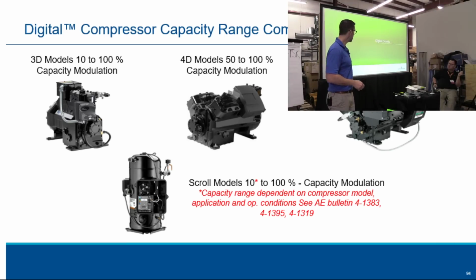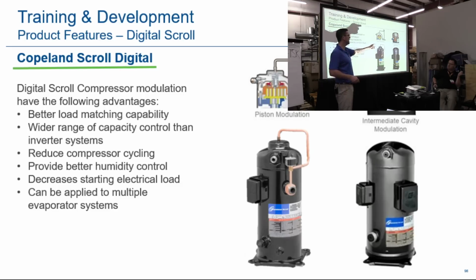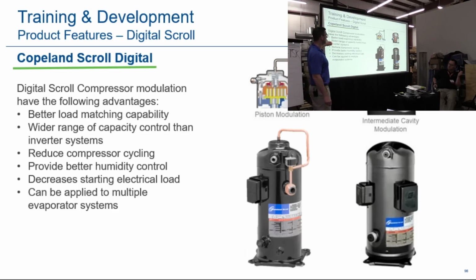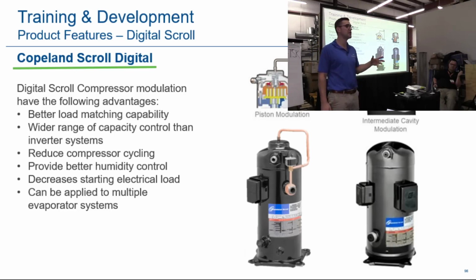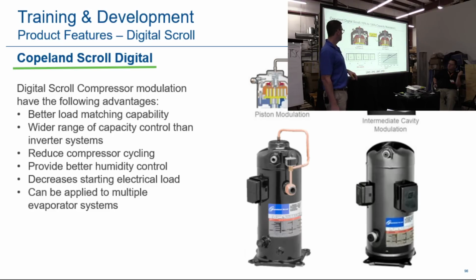Okay, digital scrolls. We have two different designs, a piston type and our larger one, an intermediate type. So you'll have a pipe outside the compressor like that with a solenoid on it. This solenoid's on the side of the compressor. They're good for better load matching, wider range of capacity, reduced compressor cycling, better humidity control, and they're applied on multiple evaporator systems. So those are some of the benefits of going with a digital. Right here is just showing how it loads and unloads on different types of cycles. So 4 seconds pumping, 16 seconds not pumping, 20% capacity.